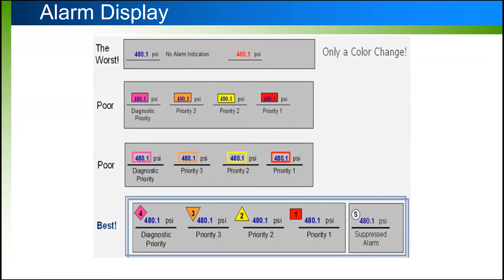Here we have an example of 4 different alarm priorities, which is one of the recommendations of ISA 18.2 alarm management, to use priorities, either 3 or 4. We generally recommend 4, using the 4th as sort of the maintenance priority. You display it differently, every alarm has a different shape and a different color.